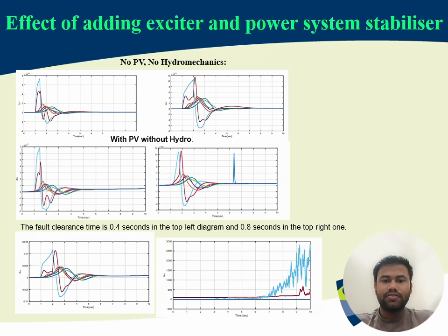This slide illustrates the effect of adding the exciter and power system stabilizer. Look at the top row of the graphs. This shows the system's unstable responses to a fault without our stabilizing controls. The system oscillates severely, especially when the fault clearance time is longer, as seen on the top right. Now simply look at the bottom row. By implementing the exciter and the PSS, we achieve stronger, faster damping of all oscillations. This proves this essential control system provides the dynamic stability necessary to ensure the entire North Queensland system remains robust, reliable, and stable even under several fault conditions.